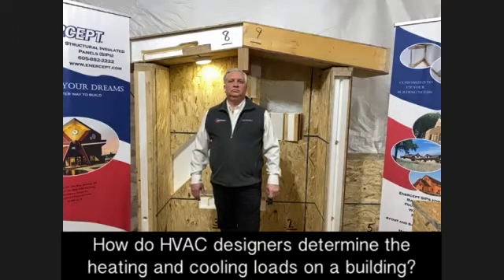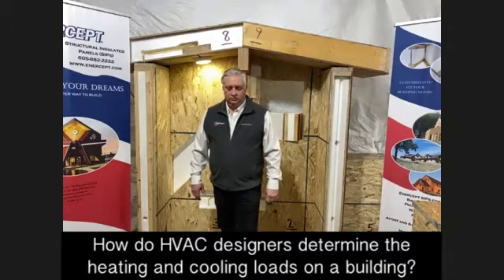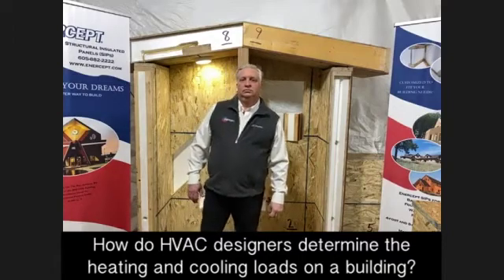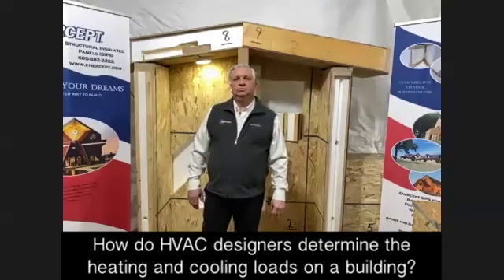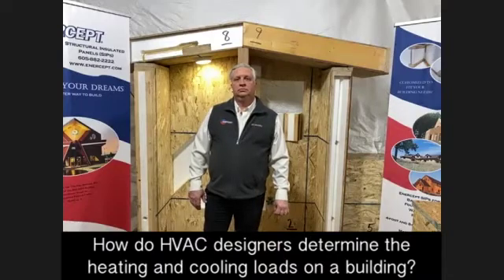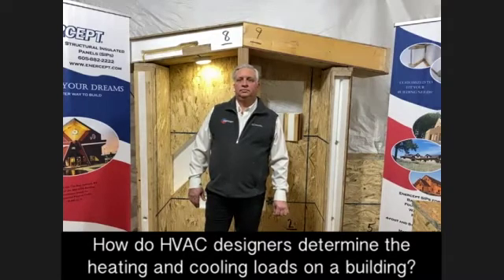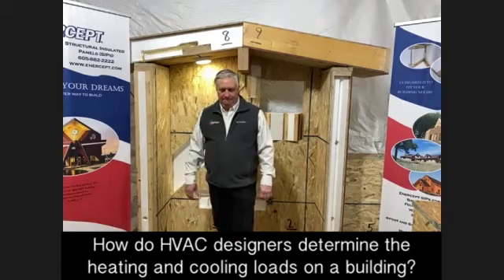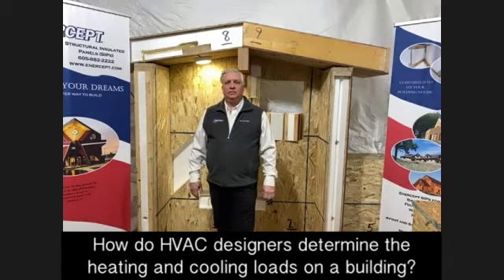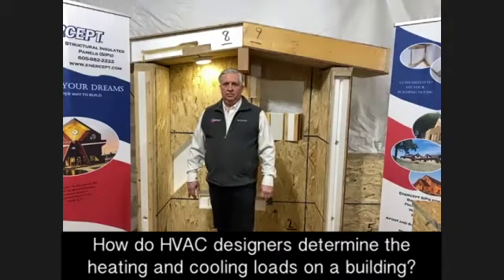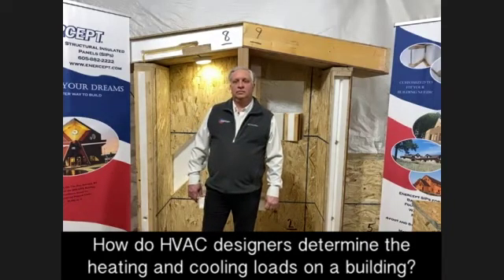And then once they've used or put all of that data into this Manual J program - it's through ACCA, the Air Conditioning Contractors of America, and it's a standardized way of determining loads on the building for both heating and cooling. They'll use that information to size what furnace and air conditioning systems are needed. And then they have another manual that you use to actually size the heating and cooling for each room based on its location in the building. So it can be a little bit onerous to go through and get the data all pulled together to make that happen, but that's really the only way that you can design a given building.